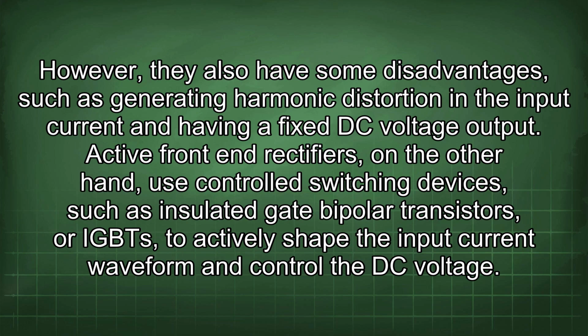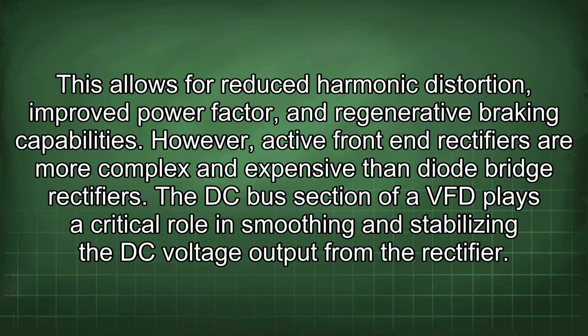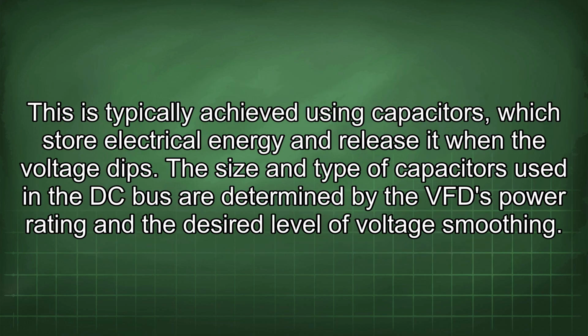IGBTs, to actively shape the input current waveform and control the DC voltage. This allows for reduced harmonic distortion, improved power factor, and regenerative braking capabilities. However, active front-end rectifiers are more complex and expensive than diode bridge rectifiers. The DC bus section of a VFD plays a critical role in smoothing and stabilizing the DC voltage output from the rectifier. This is typically achieved using capacitors, which store electrical energy and release it when the voltage dips.